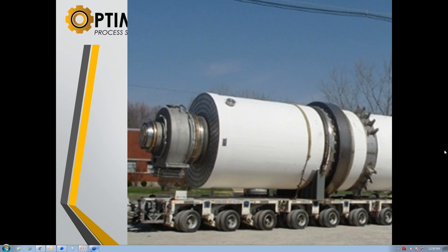That's on a slope, and the steam injection is brought in by a Kadant Johnson rotary steam joint. As the steam condenses, the condensate comes back down to this end. It goes into a sump and then is siphoned back out through that steam joint. So your steam is carrying the load. The heat transfer used is the latent heat of condensation of that steam, and the method of transfer would be radiant and conductive. It's an indirect heat dryer.